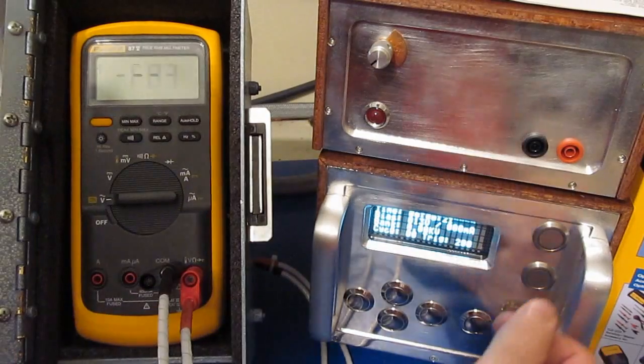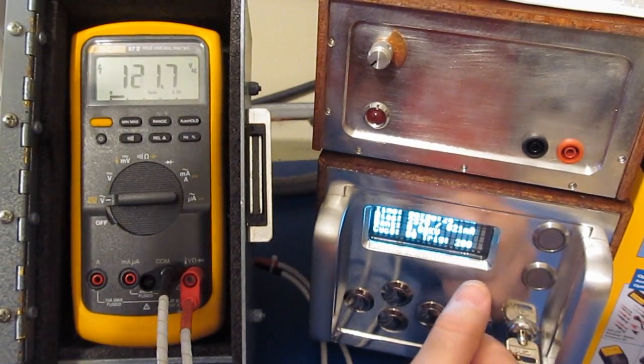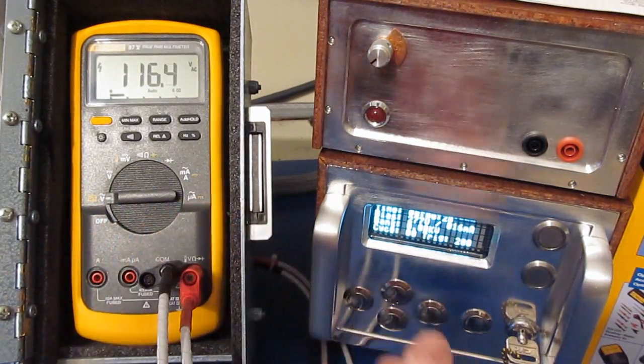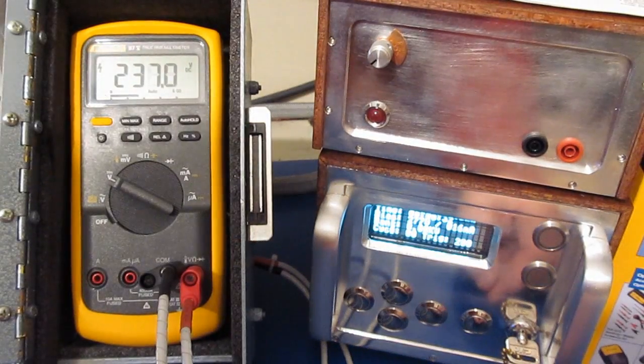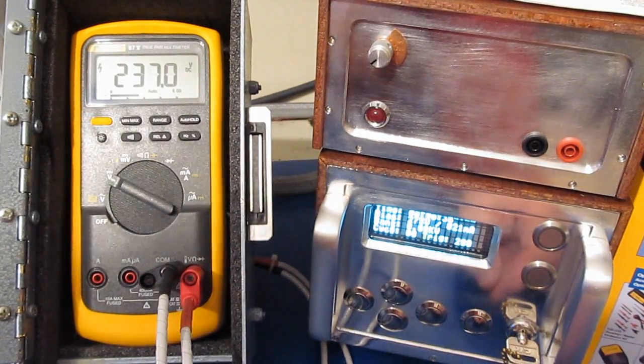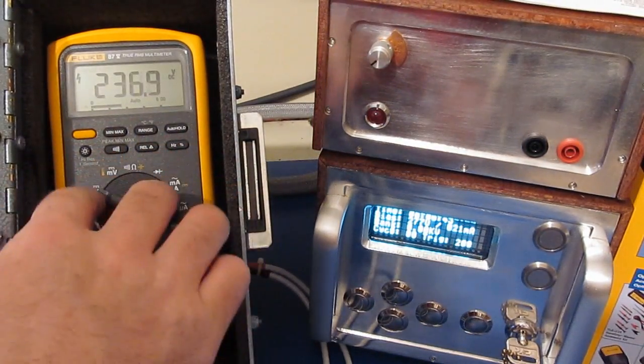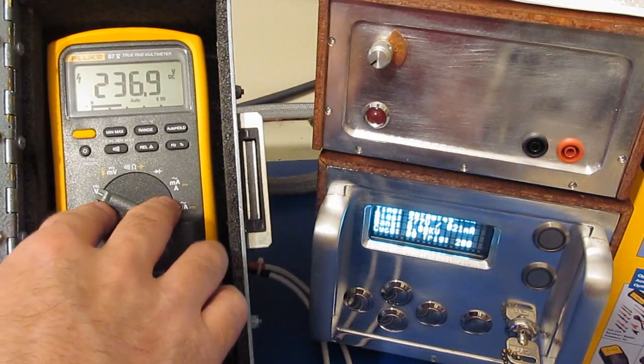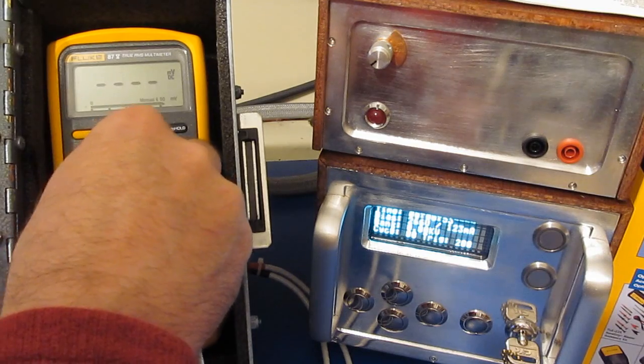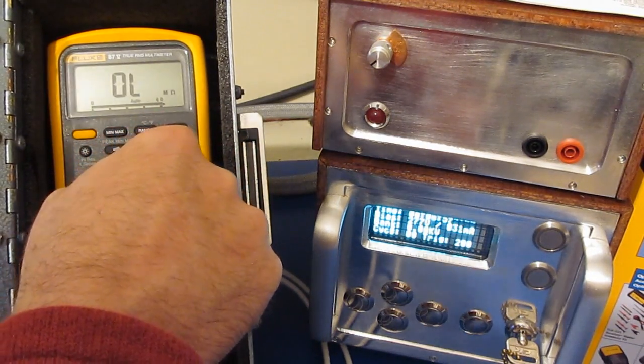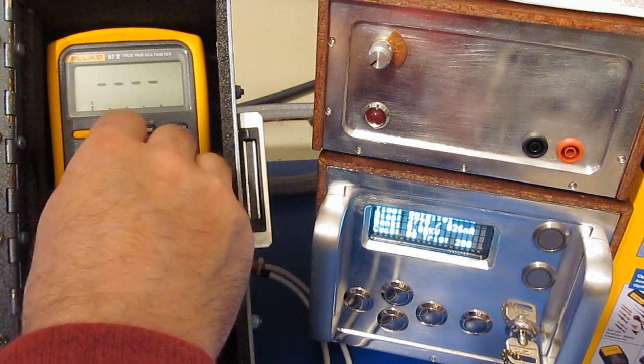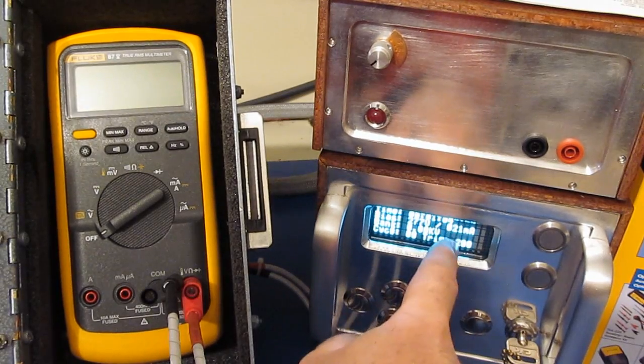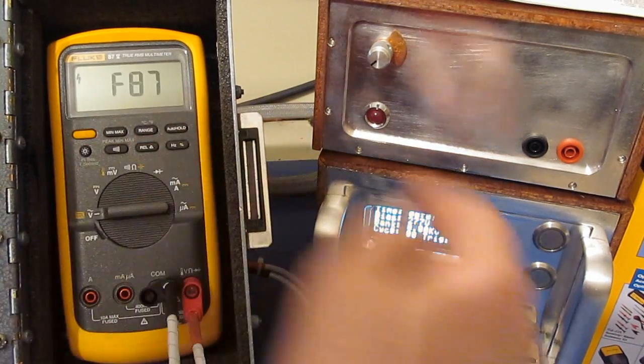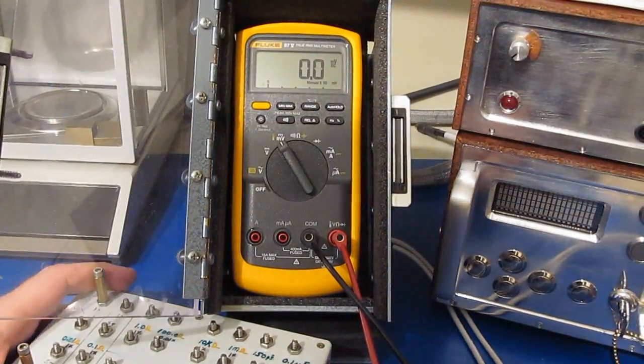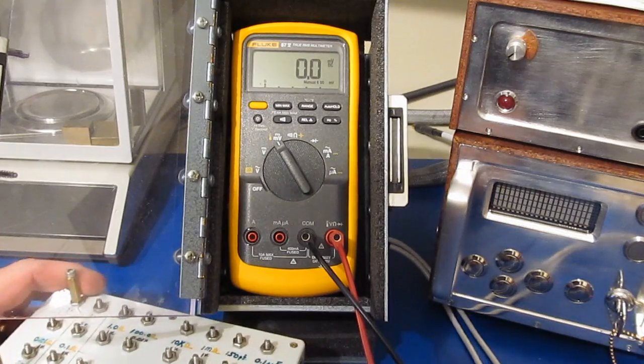So if I turn on our meter, and I'll go ahead and enable the output, you can see the AC voltage is roughly 116 volts, and the DC component is 237. What I'm going to do is just go ahead and rotate the knob through all of its settings, and then we'll functionally test it and make sure we didn't damage the meter. And again, this generator will limit the output current to, I think, about 40 milliamps where I have it set right now. So if the meter draws more current than that, the output will be disabled. Alright, so I went through and I functionally tested the Fluke 87V, and it survived that test just fine.